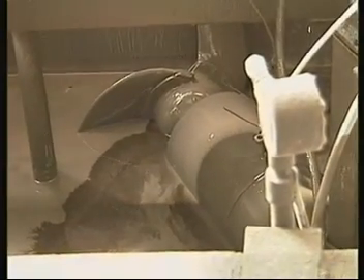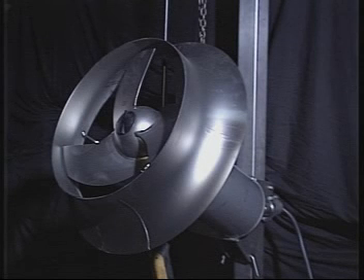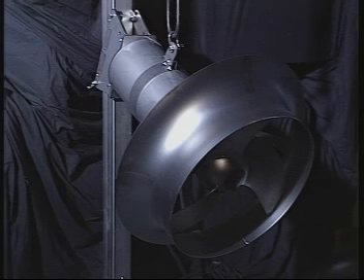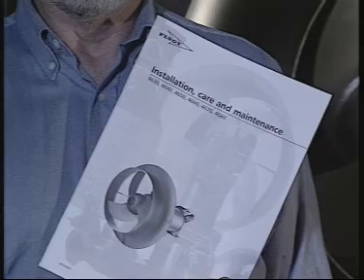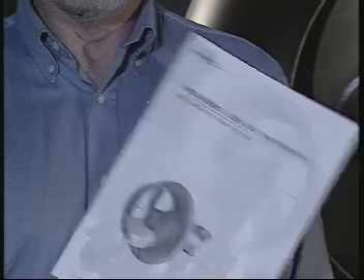We recommend different oil quantities in the mixer oil chamber depending on the mixer position. An example, the oil quantity for a 4660 positioned at 0 to plus or minus 20 degrees is 1 litre or 2 pints, and for minus 90 degrees down, increase to 1.5 litres or 3 pints. For more information, please read the Care and Maintenance Manual.